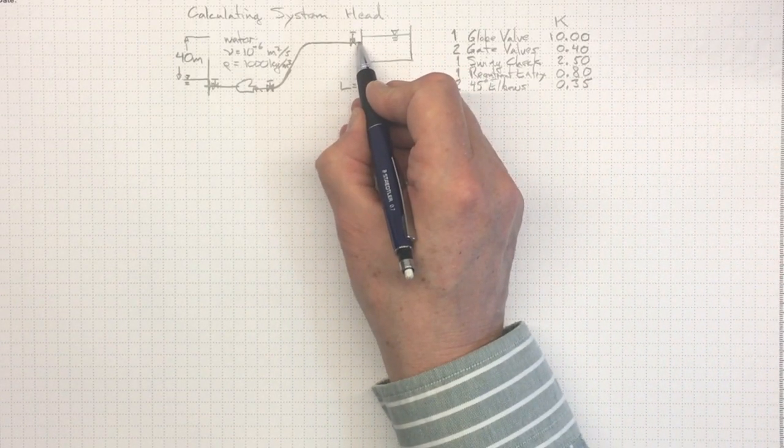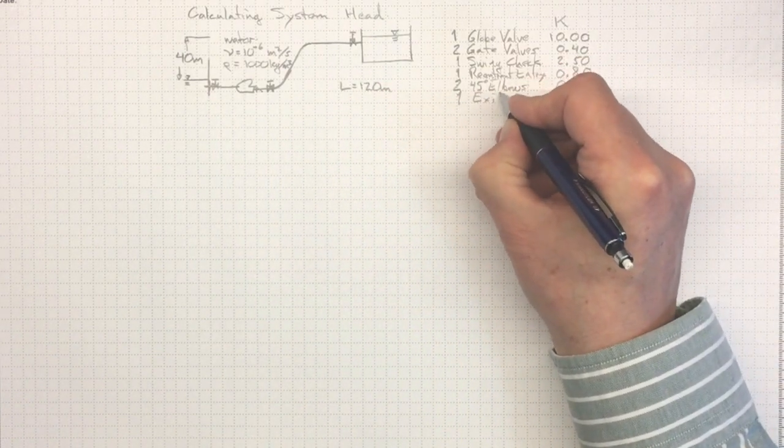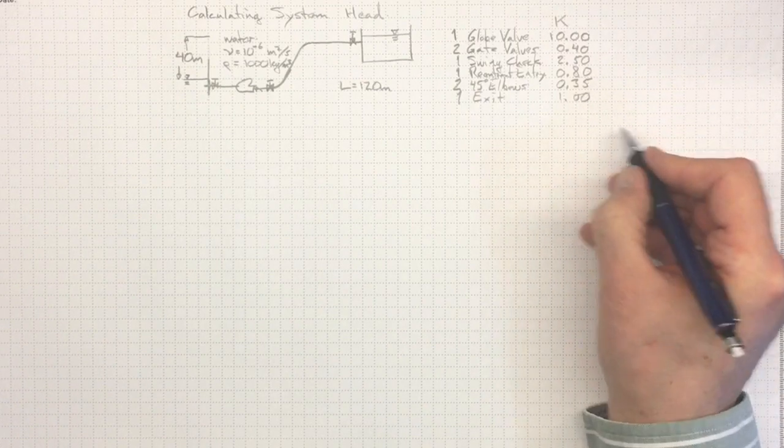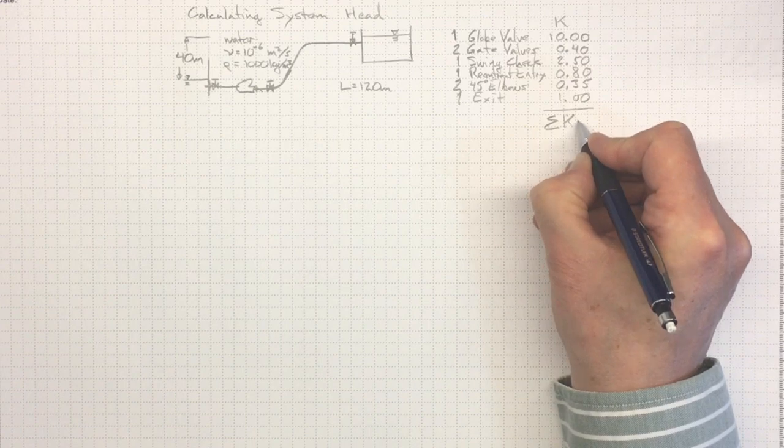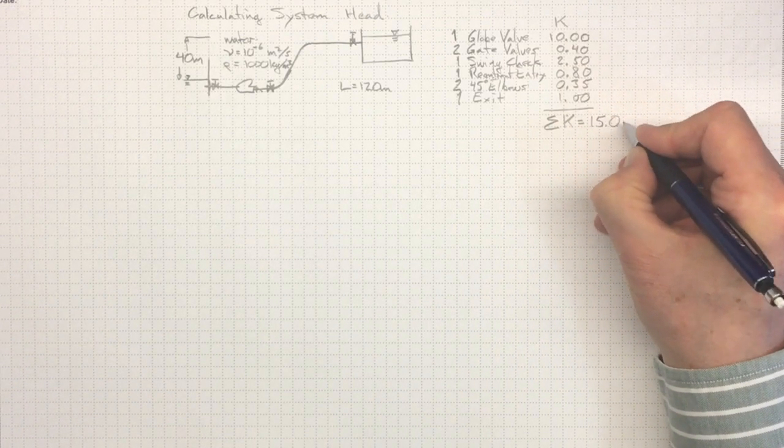Finally, the exit up here, we lose all of the kinetic energy, so the K factor is equal to 1 for an exit, no matter what shape the exit profile is. And if I sum all of those up, I wind up with about 15.0.